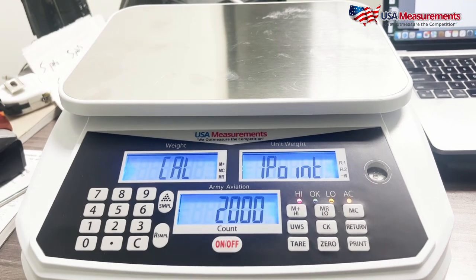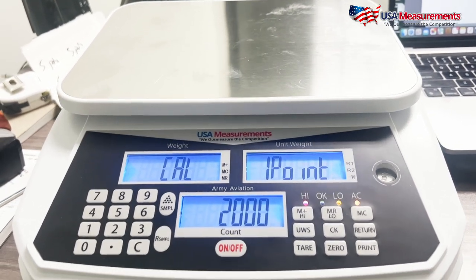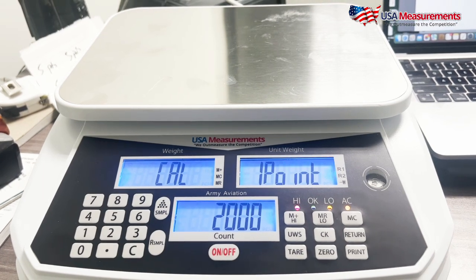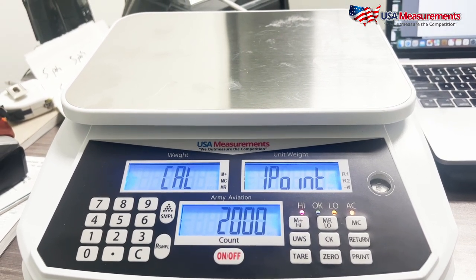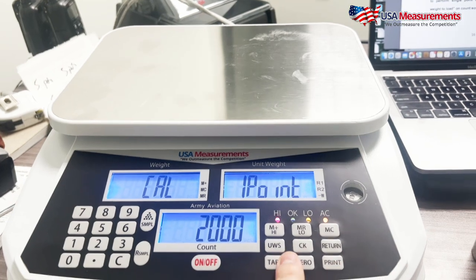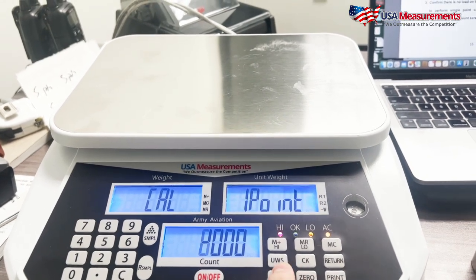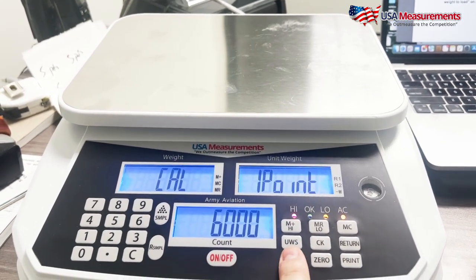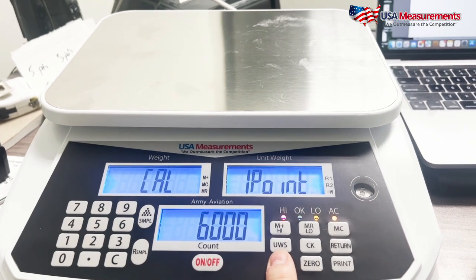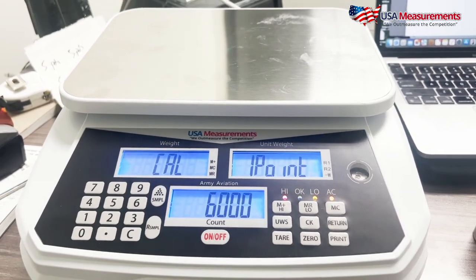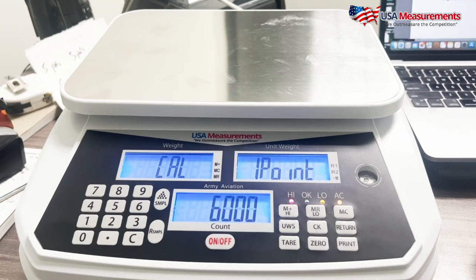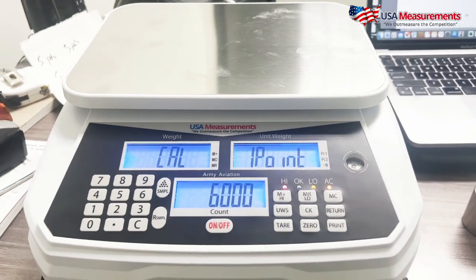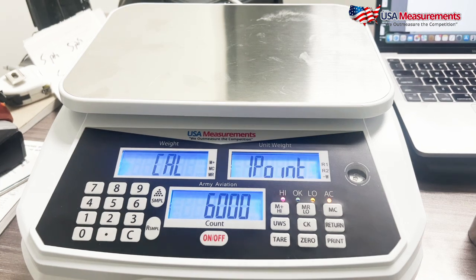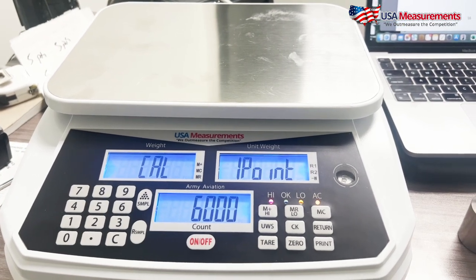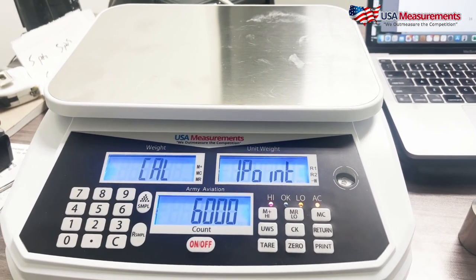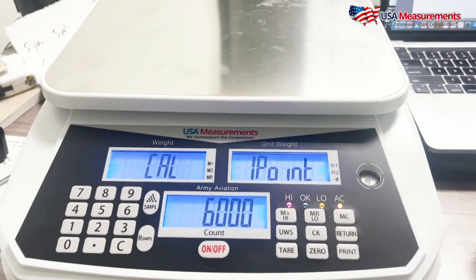This value will be associated to the amount of weight you're going to need to calibrate the scale, and it'll be 2,000 grams. Now you can change this if you want to use 4,000 grams to calibrate or 6,000 grams to calibrate. Now I personally don't have any calibration weights in grams. I only have pounds. And this still can be performed. It won't be as accurate. You just need to convert your weights from pounds to grams, or the other way around.